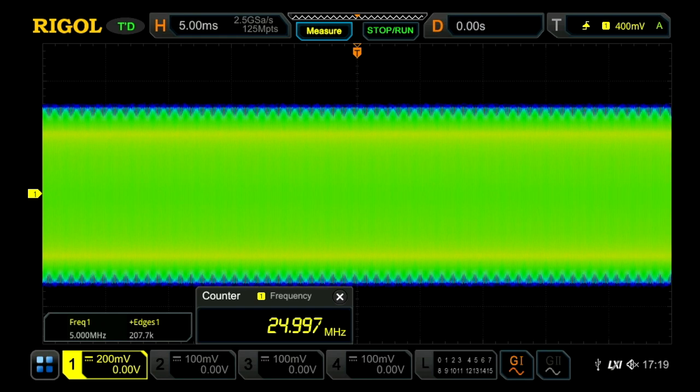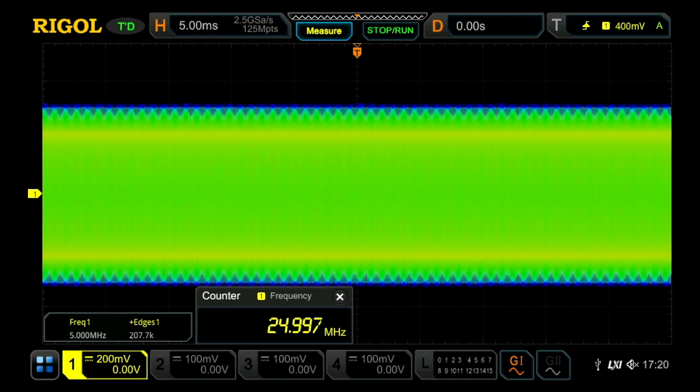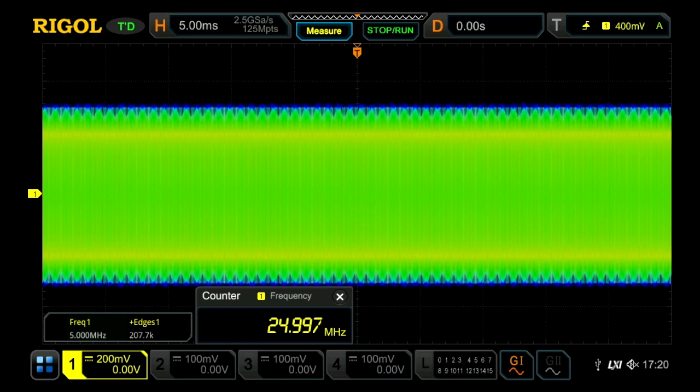If we compare that to the frequency counter, the frequency counter is accurate at 25 MHz.